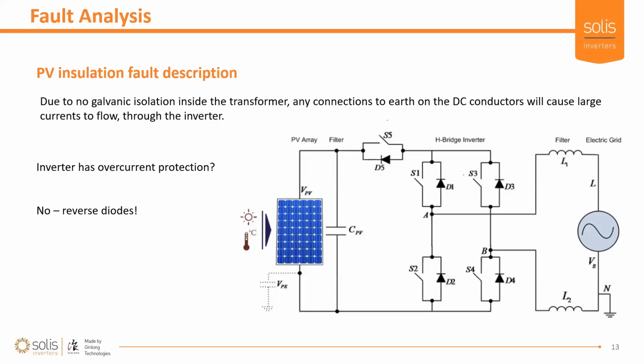These connections through to earth really shouldn't be on a system. In an ideal case, in a proper installation, you don't have these problems. So there is no need for galvanic isolation. But because there is no galvanic isolation, any connections on the DC side of the system, where the solar panel is, any connections through to earth on those conductors will be shared directly through. These switches are switching regularly and very quickly, as well as these reverse diodes. This is alternating voltage, so these could be forward biased. You would see that transformed onto your AC grid, and we should know that you can't just connect earth to a live wire. It's going to be a lot of current, and you're going to be very unhappy.